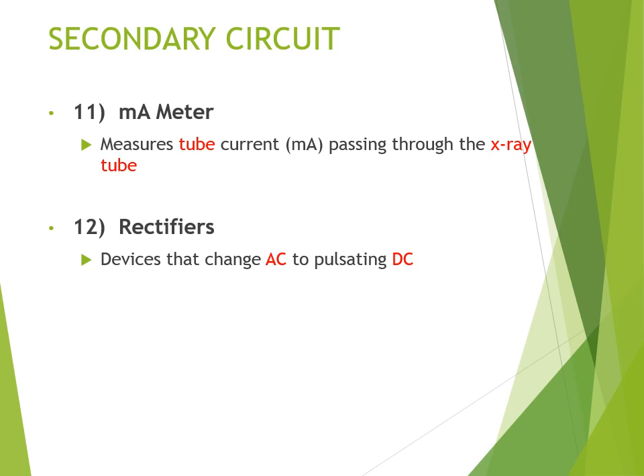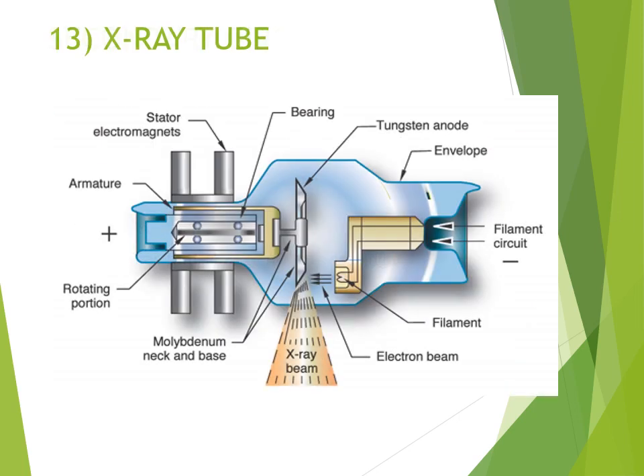Then we have a milliammeter, which measures tube current, which is mA passing through the X-ray tube. And then we have rectifiers, which convert AC to pulsating DC. And last but not least, we have the X-ray tube, which is not part of either of the circuits.